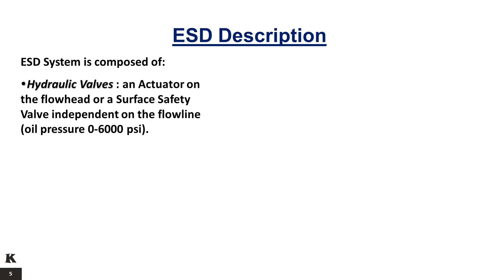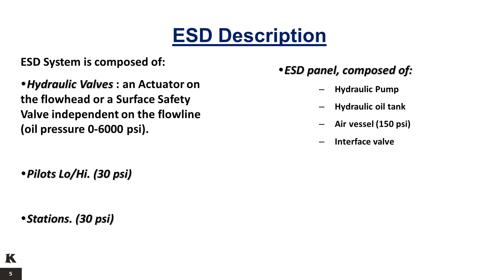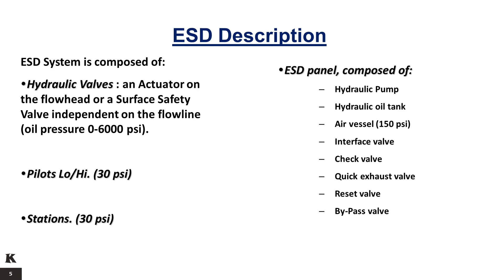The ESD system is composed of hydraulic valves; an actuator on the flow head or a surface safety valve independent on the flowline, oil pressure 0 to 6,000 PSI; high-low pilots at 30 PSI; stations at 30 PSI; and an ESD panel composed of a hydraulic pump, hydraulic oil tank, and air vessel at 150 PSI. The panel also includes an interface valve, check valve, quick exhaust valve, reset valve, and bypass valve.